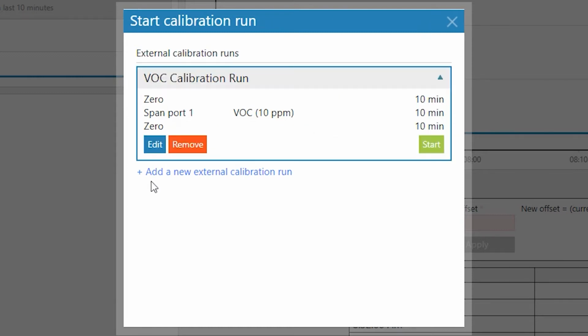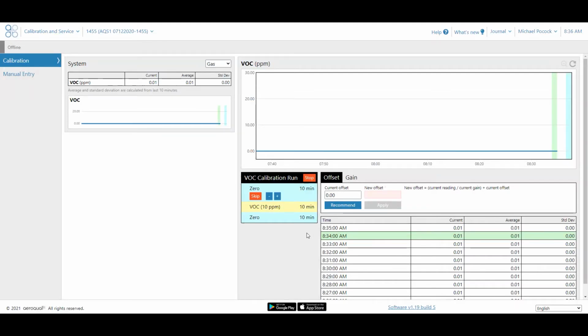When you select that, it shows you what you're doing, and it allows you to press start. It gives you some guidelines that this external calibration run is a guide. You need to manually control the zero and span, which is what we're going to be doing. So, okay, you're in here. Now you can see we've got external calibration run in progress up the top here. So you now know that you're in service mode. And here's our calibration. This arrow says what section we're in. We're in 0. So at the moment, we've got 10 minutes of being in this section, the zero air that we are feeding this monitor.